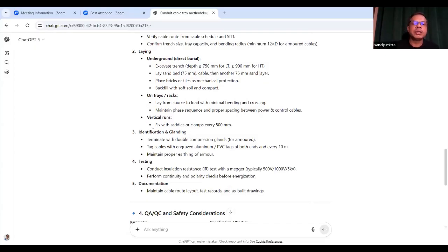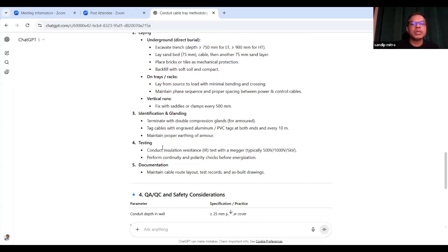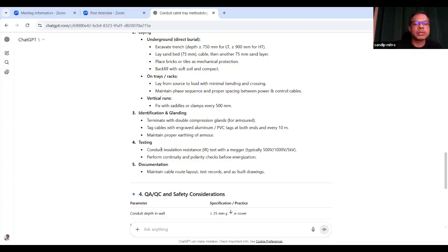If it is a vertical run, then you need to follow this process, then identification and the glanding part during termination. When you terminate the cables in the panel, terminate with double compression glands for armored cable, tag cables, and maintain proper earthing of armors.